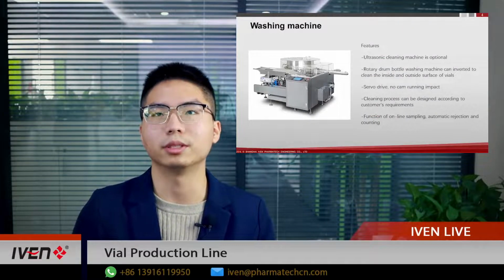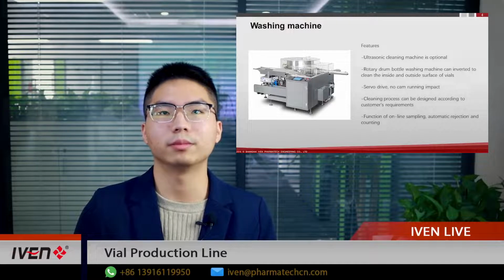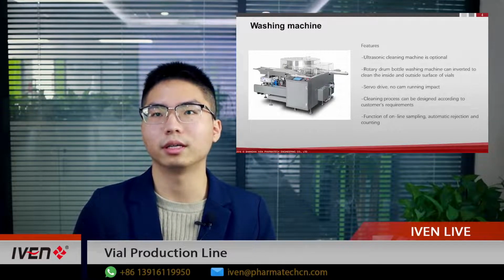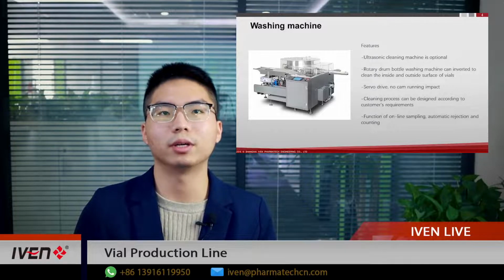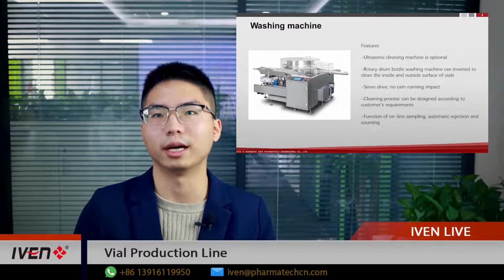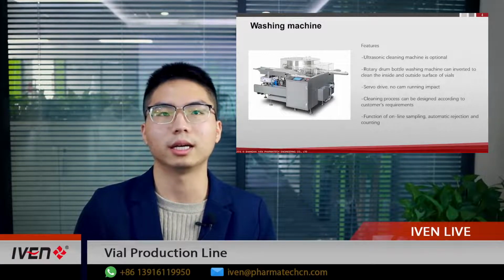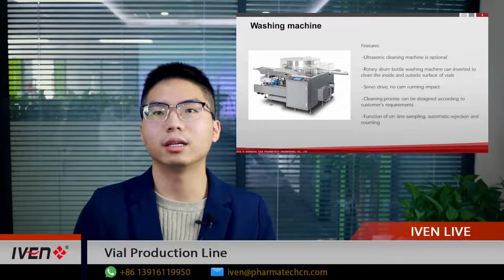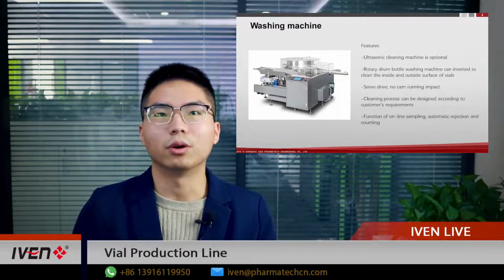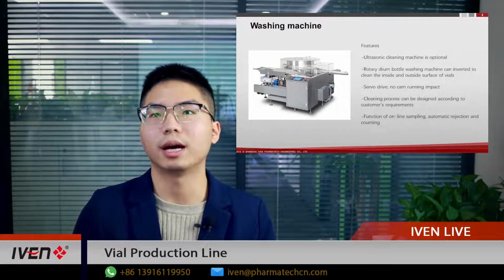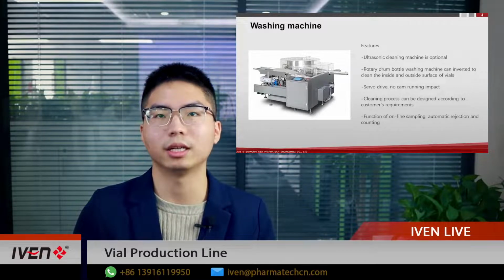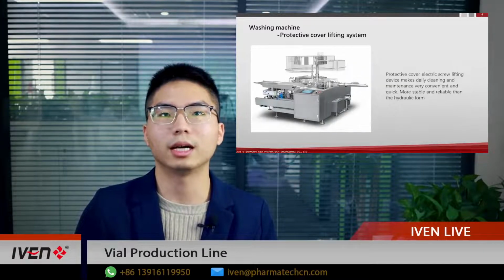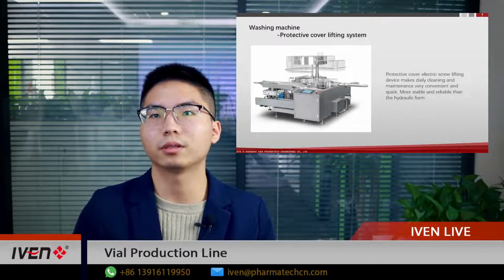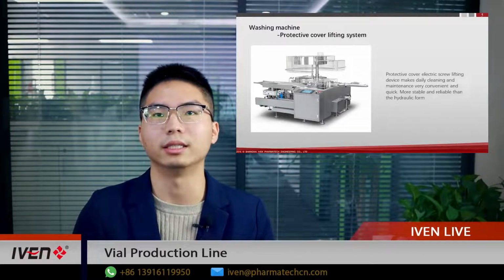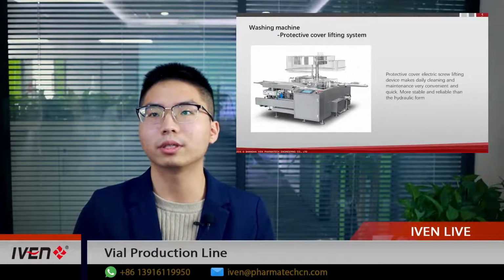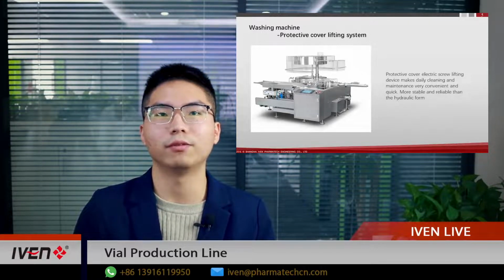First, let's come to the washing machine. The below shows some features of the washing machine. It has an optional ultrasonic cleaning function, and the rotary drum bottle washing machine adopts a servo drive, and it can invert vials to clean the inside and outside surface of vials. The cleaning process can be designed according to customers' requirements, and it also has a function of online sampling, automatic rejection, and counting. The machine has a protective cover and an electrical screw lifting device. It makes daily cleaning and maintenance very convenient and quick, more stable and reliable than the hydraulic form.